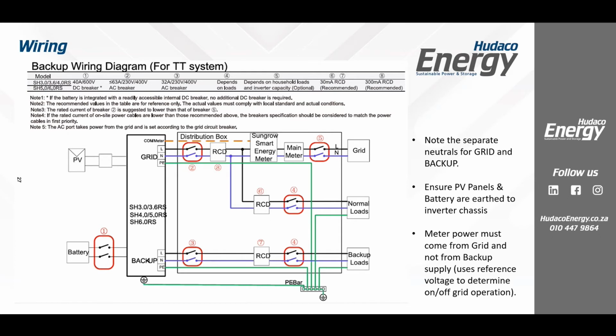The question then comes, well, do I lose communications when the grid goes away? The answer is no, you don't. And the reason you don't is because the batteries provide power to the unit. And even though it's not measuring anything coming in from grid anymore, it knows that it's got no voltage. It's still seeing the fact that there's no voltage there. And the communications dongle is powered from this side. So it's measuring how much energy am I getting from battery, how much energy am I getting from PV, and how much energy am I pushing to my backup loads, and it still reports all this data to you. The only data that's then missing is this from grid, which is 0. Okay, so you don't suddenly stop getting information. You actually keep all that information going.